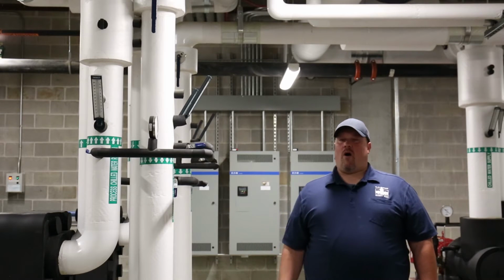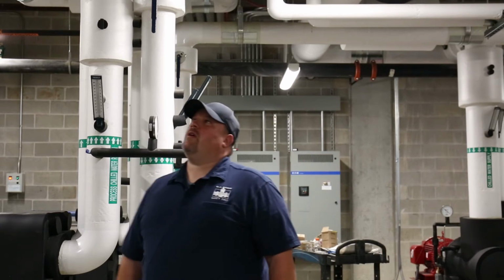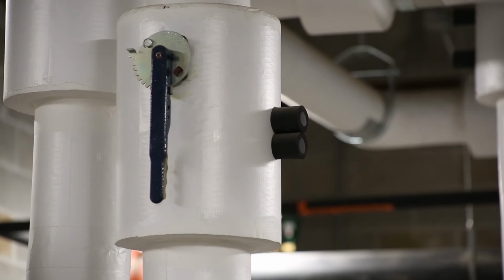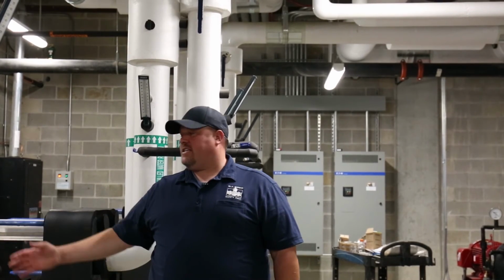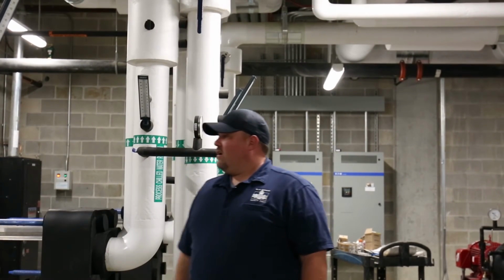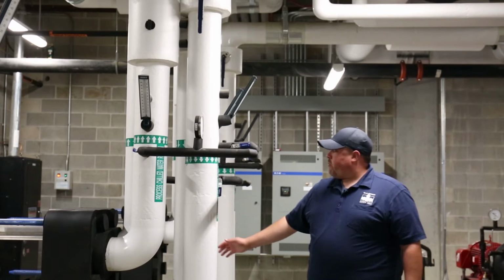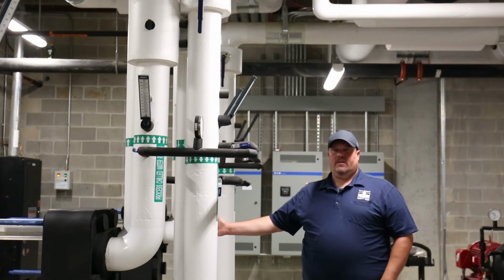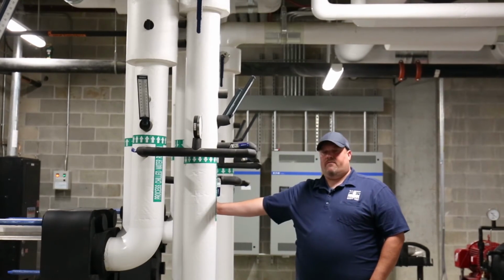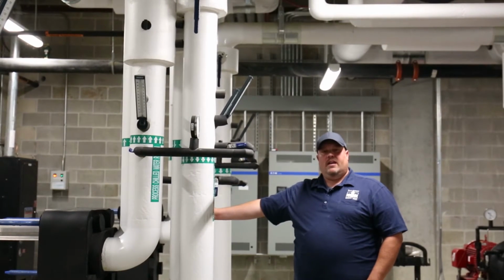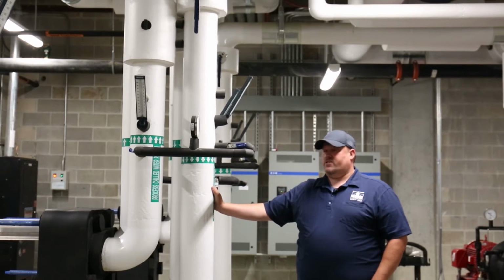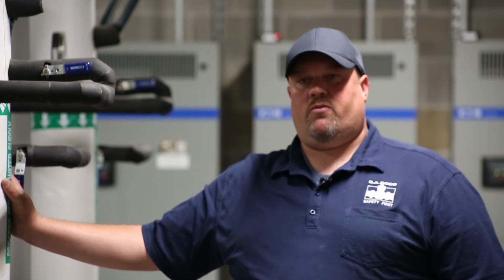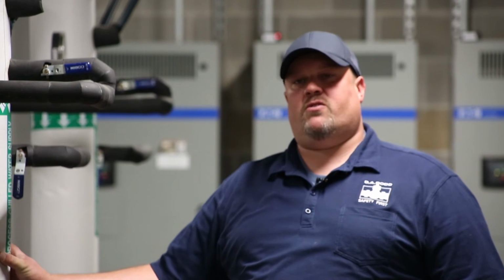Here's our process chilled water pumps. They also are included with automatic flow control valving and suction diffusers, as well as pressure differentials, chemical feeders, and test coupon racks. They circulate the water through our process chilled water exchangers that transfer the chilled water from the campus loop and or our heat rejection chiller to the process chilled water loop to run throughout the building to the several different drops in the labs for future Haskris connections.